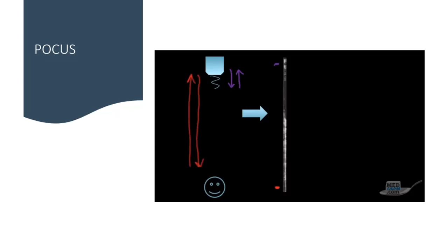Depth is a function of distance to the ultrasound machine, meaning the longer that it takes to return to the ultrasound machine means it had to penetrate deeper into the tissues, and the ultrasound machine knows to place those returning echoes deep in the scan line. Conversely, the more shallow that the ultrasound wave must penetrate and reflect back, the less time it takes to return, and therefore the ultrasound machine knows to place that more shallow on the scan line.